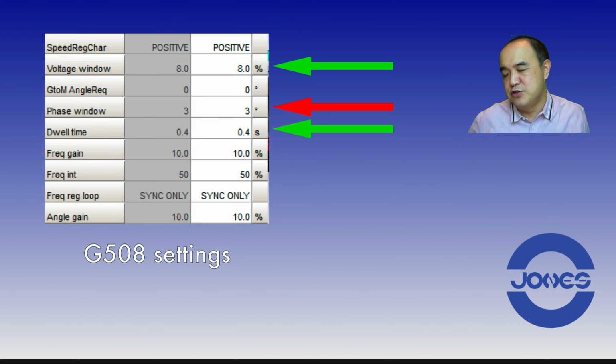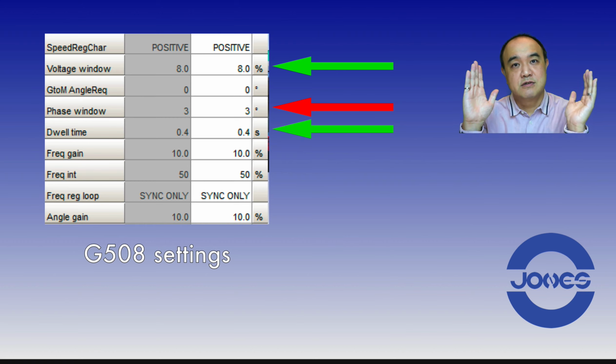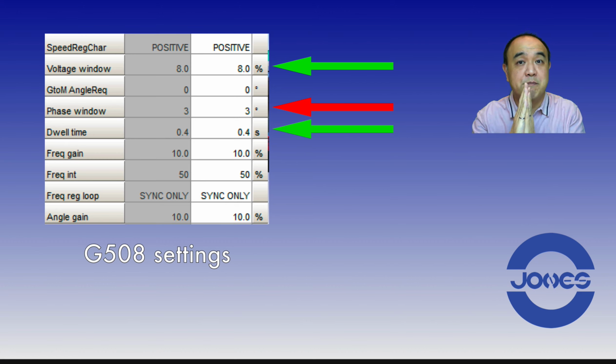When they tested the engine in the factory, they tested, of course, on a water brake or a dummy load, which is resistive, so everything is stable, the load was not fluctuating, and at 3 degrees, the breakers would close very peacefully and nicely. That's why they set it up like that at the factory, but when you run it on the site, things are not always so ideal.